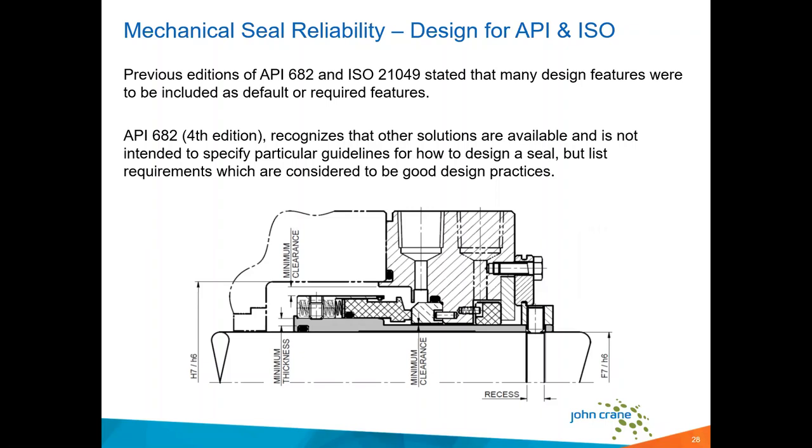The exception is going to be made around pumping ring clearances and flow diverters and things of that nature. But on smaller pumps, the radial clearance is a little more difficult to achieve. So the fourth edition considered, for example, size range and relates clearances to pumps used in both 610 and ASME B73, so your ANSI pumps as well. The intention is now to take what's considered a good design practice and apply that across different industries, both API 610 equipment and ANSI equipment.